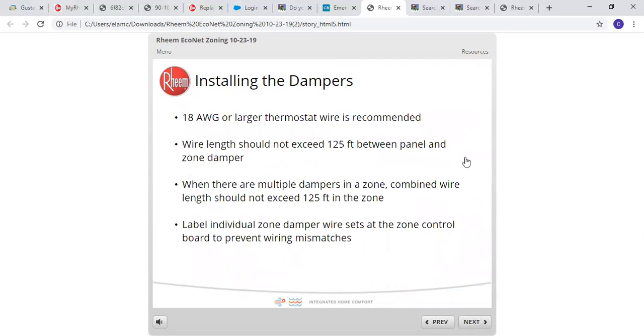They're recommending 18 gauge or larger thermostat wire. Wire length should not exceed 125 feet between the panel and the damper. And when there are multiple dampers in a zone, combined wire length should not exceed 125 feet in that zone. Label individual zone damper wires at the zone control to prevent mismatching wires. So make sure they're all grouped together per zone.